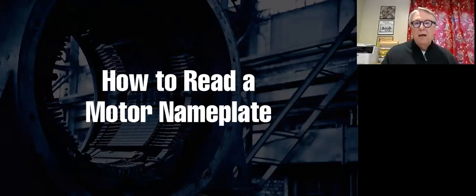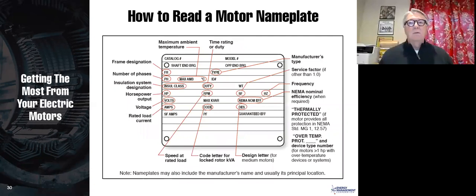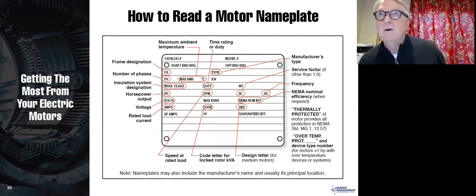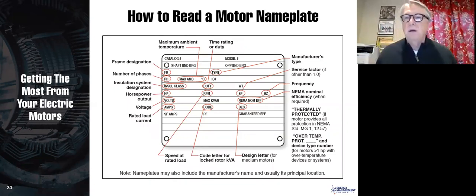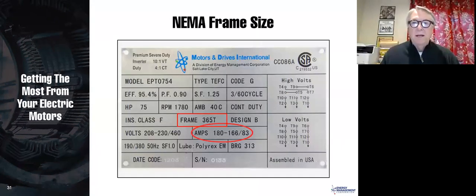So let's talk about a motor nameplate. Here is a motor nameplate. The National Electrical Code specifies what needs to be on a motor, but they specify the minimum information that needs to be on a motor, and most motor nameplates will have additional information above and beyond the minimum that's required. Here's a motor nameplate, and we will be talking about this as we go through this presentation. We're going to try to talk about what all those different items on a motor nameplate mean.